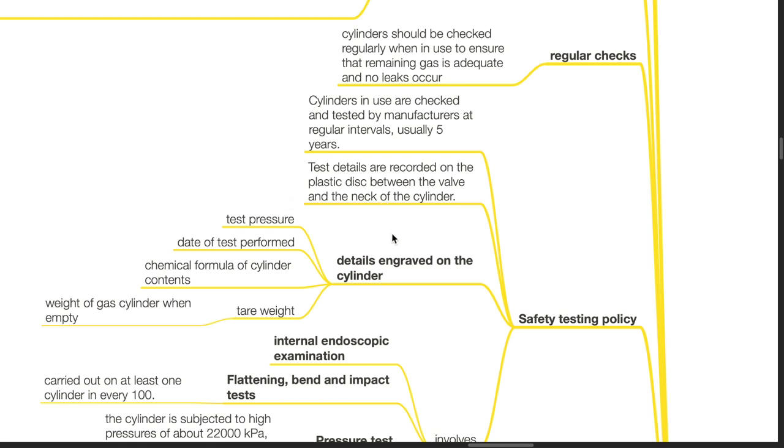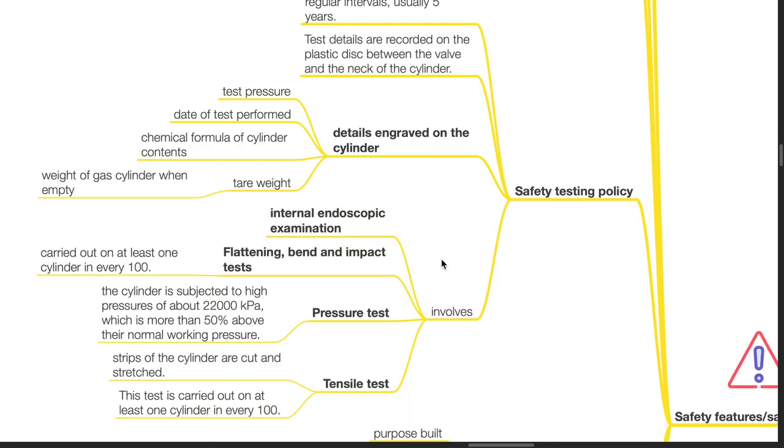Details engraved on the cylinder includes test pressure, date of test performed, chemical formula of the cylinder contents and tare weight which is the weight of the gas cylinder when empty. Safety testing involves internal endoscopic examination, flattening, bend and impact test carried out on at least one cylinder in every 100, pressure test where the cylinder is subject to high pressures of about 22,000 kPa which is more than 50% above their normal working pressure, and tensile test where strips of the cylinder are cut and stretched. This test is carried out on at least one cylinder in every 100.